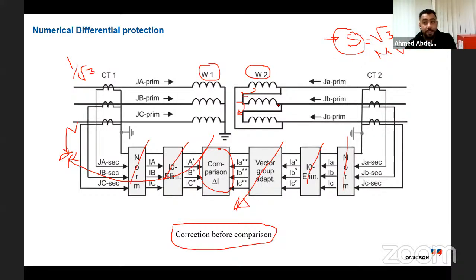But a lot of errors will happen during the normal operation of the transformer. I need to take care of it to avoid the system or the transformer tripping in case of normal operation. So what should I do? I should take it into consideration during the calculation of the relay settings. So what will happen? We define 2 elements. The first element I defined is the differential current, the output of the comparison between the high side and the low side.